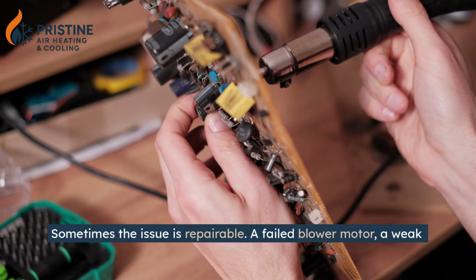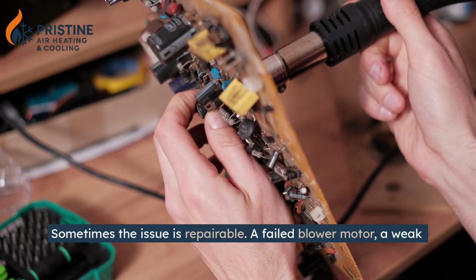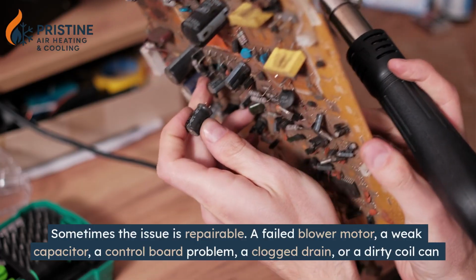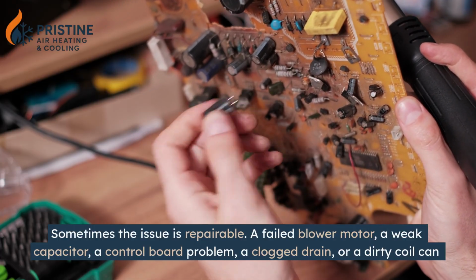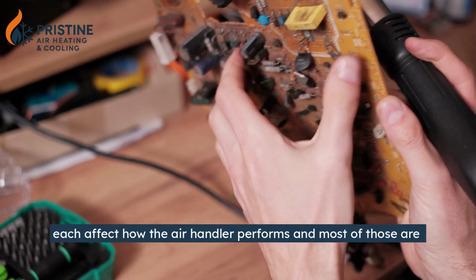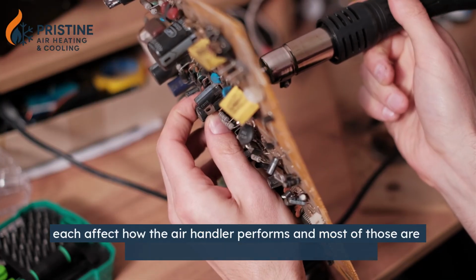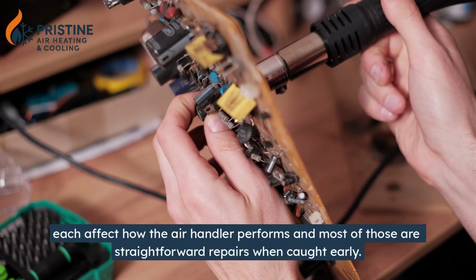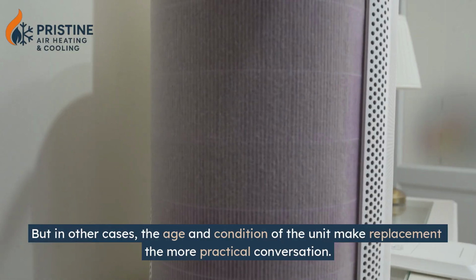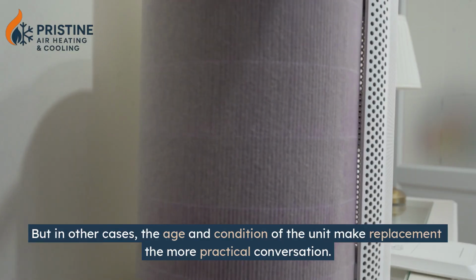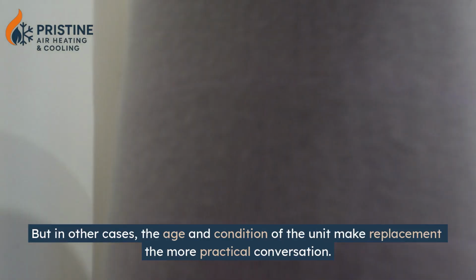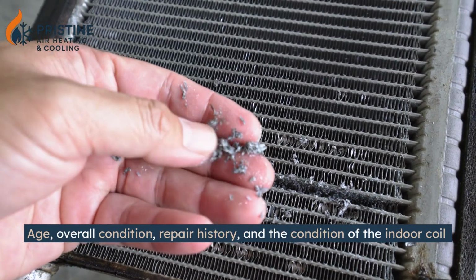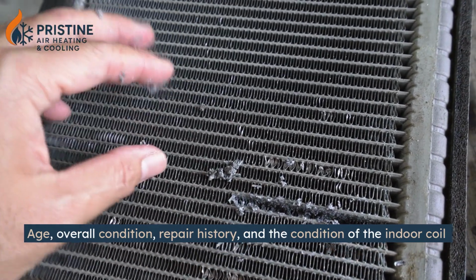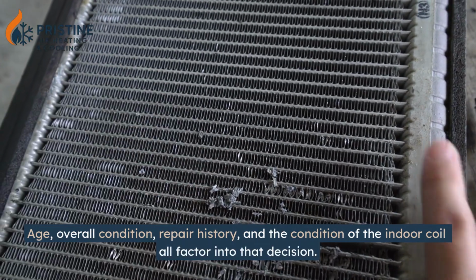Sometimes the issue is repairable. A failed blower motor, a weak capacitor, a control board problem, a clogged drain, or a dirty coil can each affect how the air handler performs, and most of those are straightforward repairs when caught early. But in other cases, the age and condition of the unit make replacement the more practical conversation. Age, overall condition, repair history, and the condition of the indoor coil all factor into that decision.